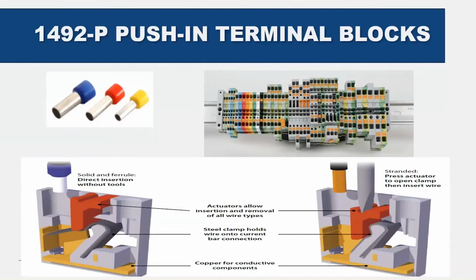The 1492P push-in terminal block, in case somebody doesn't know what a push-in terminal block is, it can accept ferruled wire or solid wire directly into the block without the use of tools. If you're using stranded wire, you would have to pull the actuator back and insert the wire. Just as if you want to take the wires out, you would pull the actuator back with a screwdriver and take the wire out. We'll go into a little more detail.